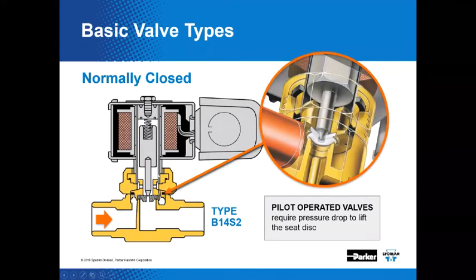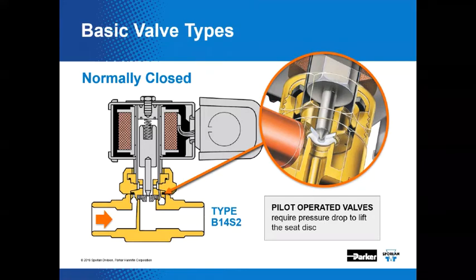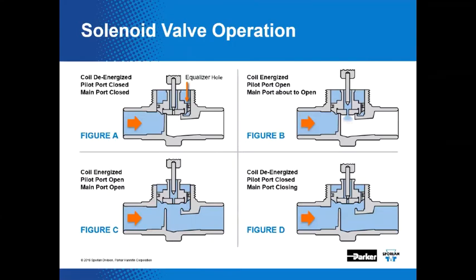The second type is pilot-operated: when you apply current to the coil and move the plunger, that opens a pilot port, which allows line pressure to assist in opening the valve and allow full flow. In a pilot-operated valve, the stem and plunger assembly opens a pilot port, releasing pressure that may be on top of the disc. The disc then moves upward, allowing the main valve port to open. Next, we'll go through the four phases of operation for a pilot-operated solenoid valve.